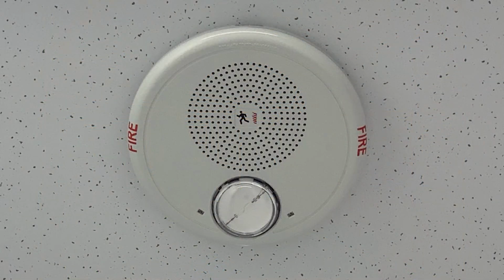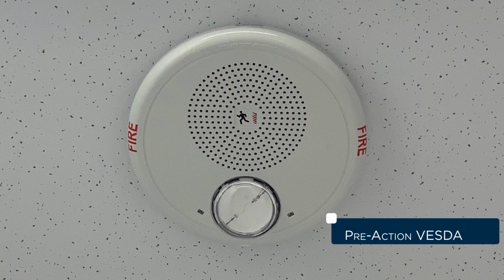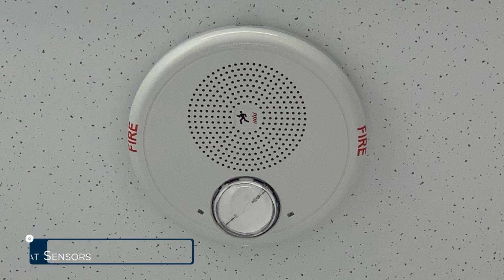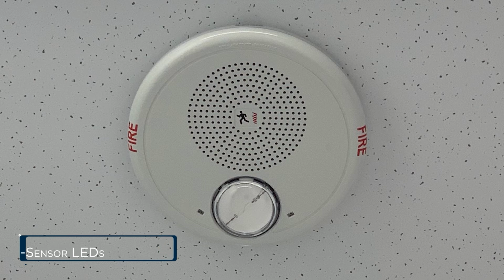The fire system is a dual interlock dry pipe pre-action system, VESDA system, which is separated by zones. We utilize duct detection and heat detectors, and the fire alarm system sends notice to building annunciator panels as well as the monitoring company. We implement full cold aisle containment in all customer spaces, install heat sensors that are monitored 7 by 24 by 365, and have humidification installed throughout the data center to meet the industry standards. We also employ motion sensor LED lighting throughout the facility.